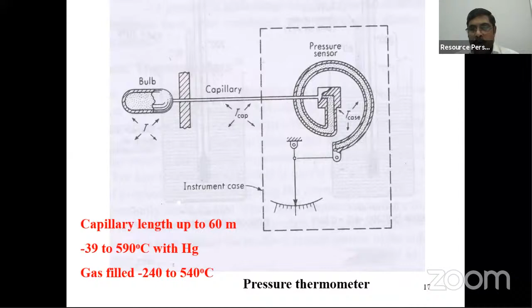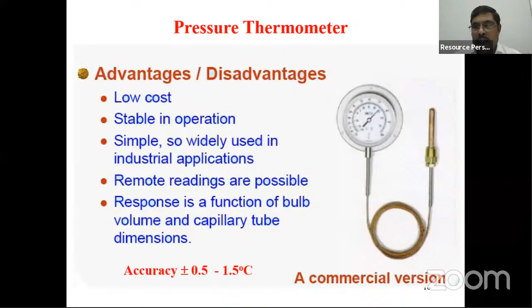The advantages are basically for all of these thermometers: the glass and mercury thermometer, the bimetallic thermometer, and the pressure thermometer. These are all passive type instruments. They do not require external power to operate, and they provide stable operation. The only thing is these instruments are meant for steady state temperature measurement. If your quantity is varying with respect to time, of course you cannot use them. And again, for a remote location it's difficult. But if you have a long capillary, you can also go for a remote sensor. This is typically used in air conditioning equipment and many other applications. You can find this sensor there.